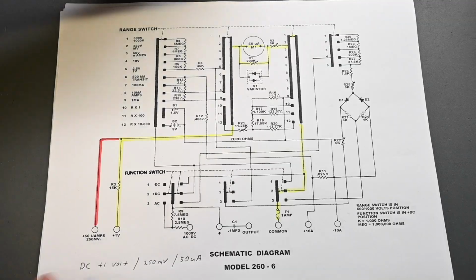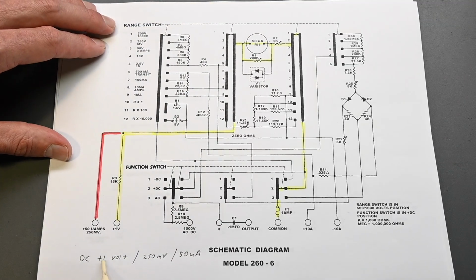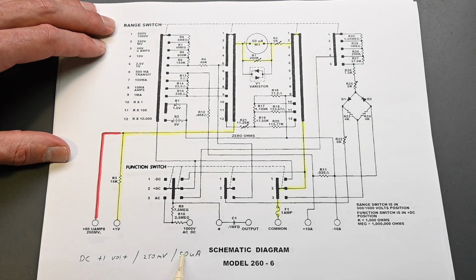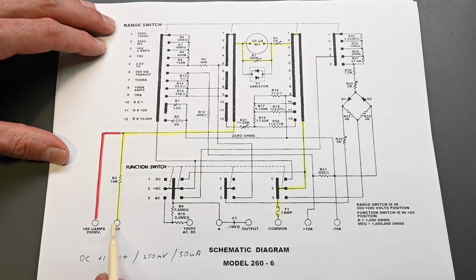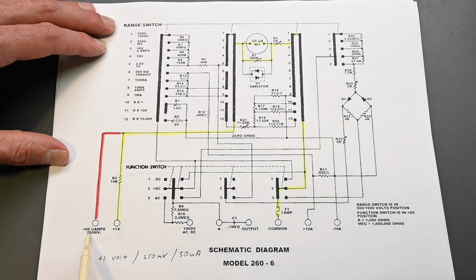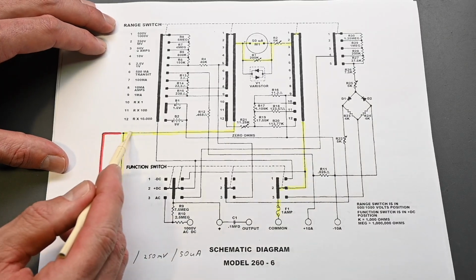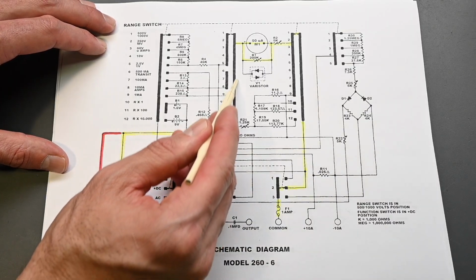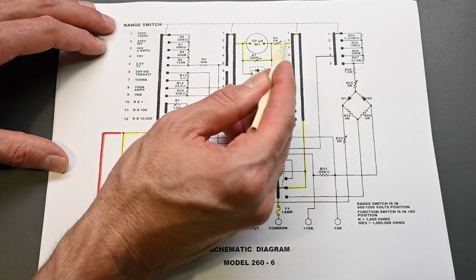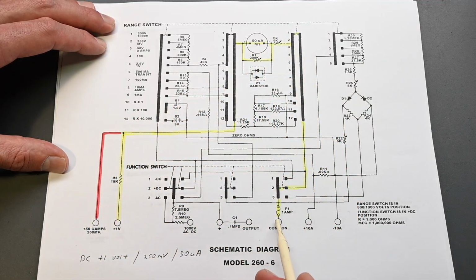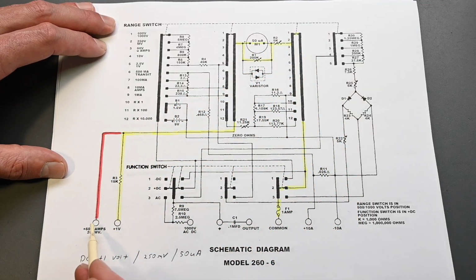All right, so taking a look at the DC positive 1 volt, 250 millivolt, or 50 microamp input, you're using these inputs over here instead. You can see on the 50 microamp or 250 millivolt input, it comes over here, just comes directly to this side of the switch, comes right up to the meter, through the meter to the other side, down into common. So this is the most direct input you can have to the meter, the most sensitive position.